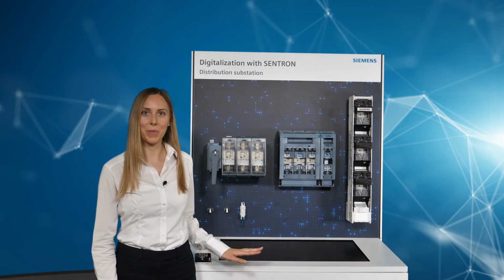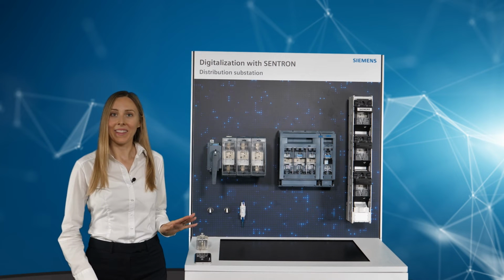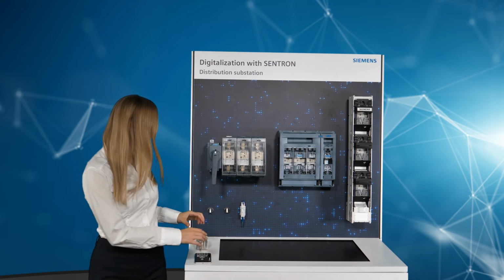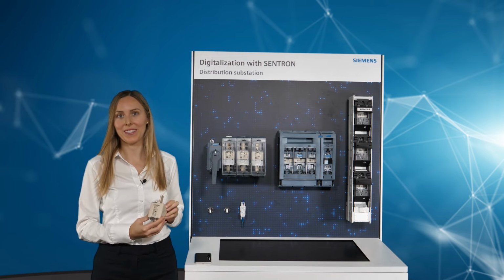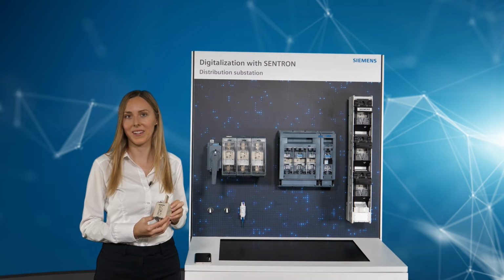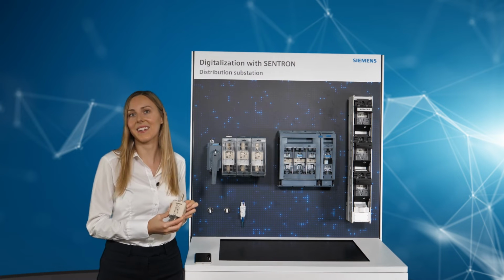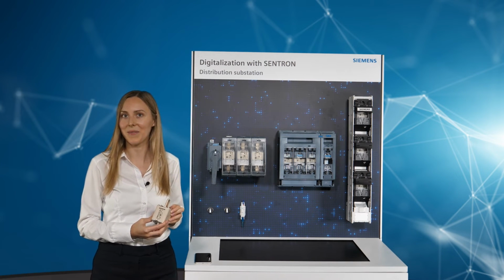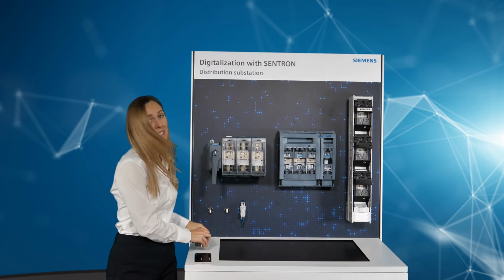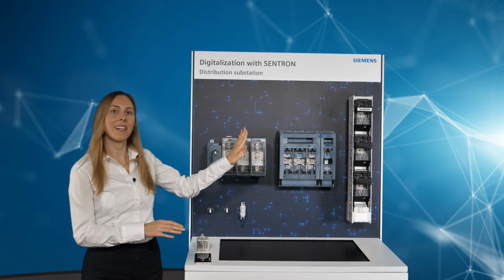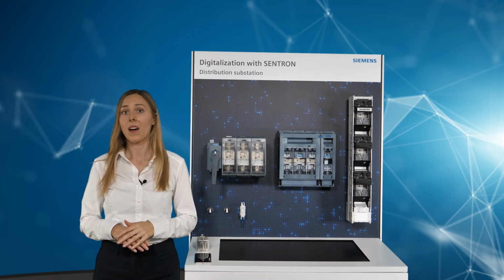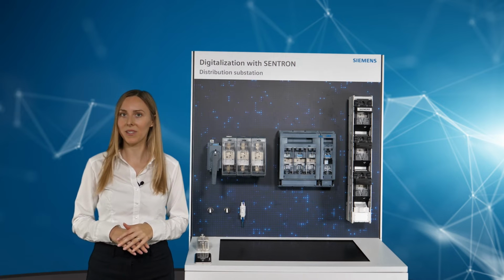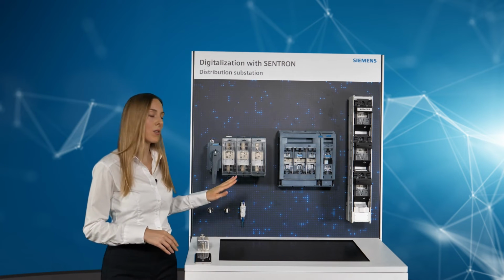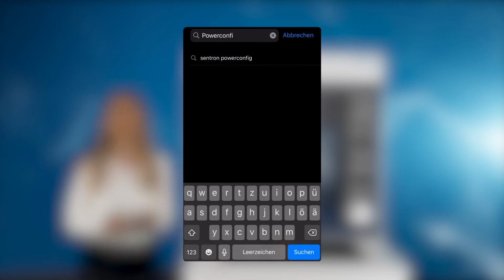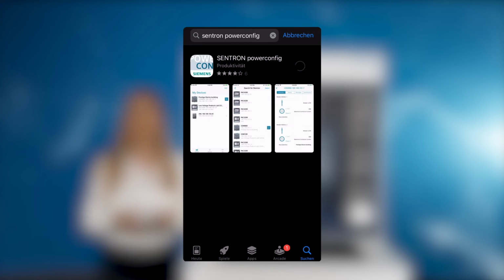We are now making our distribution substation digital. Therefore, all you have to do is replace the normal fuse with the 3NA COM fuses that have the measuring and communication function. Since the design and the size is exactly the same, it is very easy to replace. So this has already been done, the fuses have been changed, and in all of the devices, we now have 3NA COMs. Apart from that, we need a 7KN Power Center 1000, which has to be connected to 24 volts in order to run. So, first, I download the PowerConfig mobile app that I basically find in every app store.